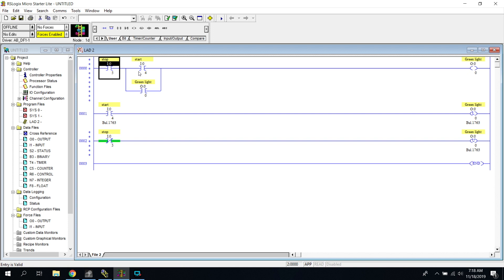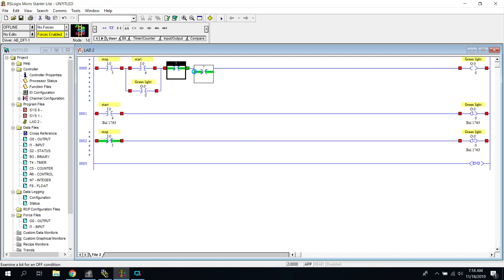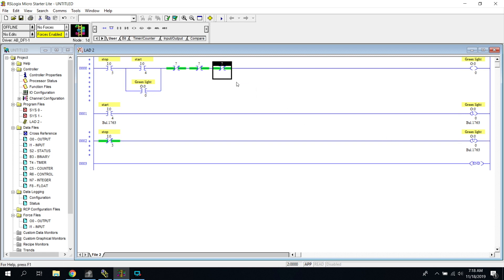All right. Same thing goes for the start. It needs a signal from it to start it up. The reason we would like something more like this is because now we can add limit switches into our circuit here. So we can start adding, these could all be limit switches, and we can do 10 limit switches per se, or we could do dead man switches or something like that. That might be a safety and it's conditional.